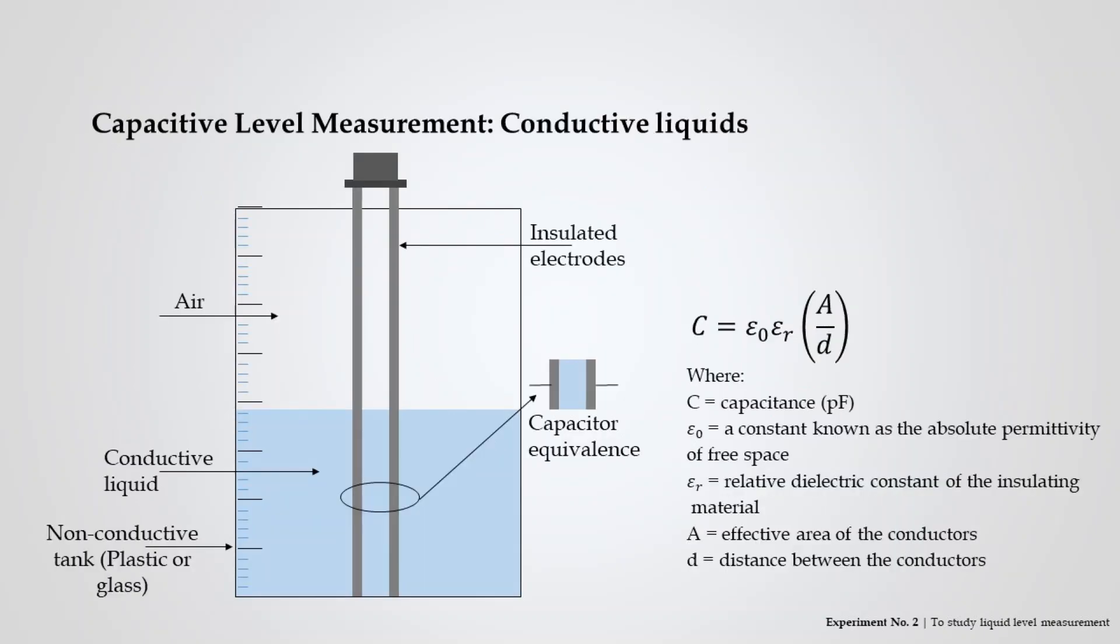The level measurement setup of conductive liquids consists of a non-conductive tank usually of plastic, glass, or acrylic in nature. Two insulated metal electrodes are placed apart from each other. The liquid used for measurement should be strictly conductive in nature. The two insulated electrodes act as two plates of a capacitor with air and water acting as a dielectric material separating them. The capacitance developed across these two electrodes is represented by the equation shown below. This capacitance is directly proportional to the liquid level in the tank.